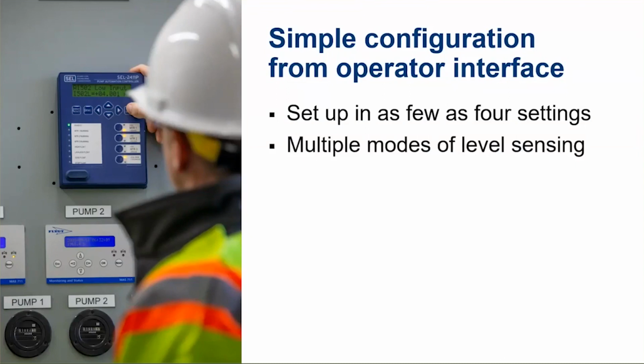In this selection process, you have multiple modes of level sensing. You can have a level transducer with 1 or 2 or all backup floats, or you can just have a float application for controlling a duplex up to a triplex lift station. There's also fault detection involved in this simple settings file that it creates. It's going to check to see if your transducer is good or not, and if it fails, it automatically fails over to the backup floats and operates the station. If you lose a pump, it automatically is going to promote those other pumps to make sure that that station is always under control and is always operating as efficiently as possible. Anytime it detects a float out of sequence, it's going to go ahead and operate in that mode with the floats that it has available to operate.